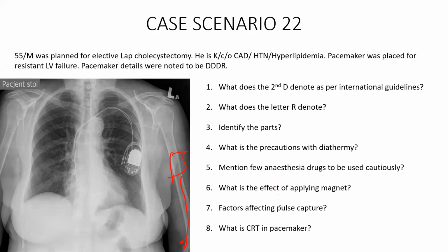Very good. Bipolar is safe. Unipolar can be used, but make sure it is at least 15 centimeters away. A single burst should not last more than 2 seconds, and the subsequent burst interval should be a minimum of 15 seconds. And try to make sure the current circuit is well away from the cardiac axis.